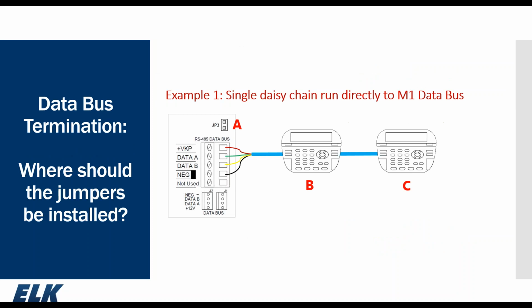Okay, we're going to take a slight quick quiz here. We're going to give everyone time to look at this example here. In this particular example, if we have a single daisy chain run directly from the M1 out to, say, 2 keypads, where would you install the terminating jumpers in this scenario? That's a single home run, 2 devices. So we would want to make sure to install the jumper on A at the panel, JP3, and then the last device would be terminated. Now this length from M1 out to this last keypad could be that maximum 4,000 feet.